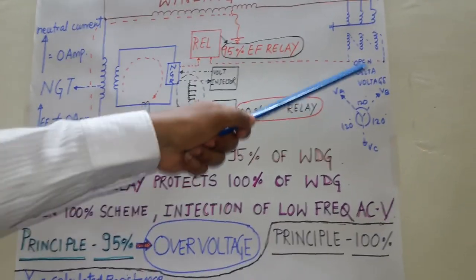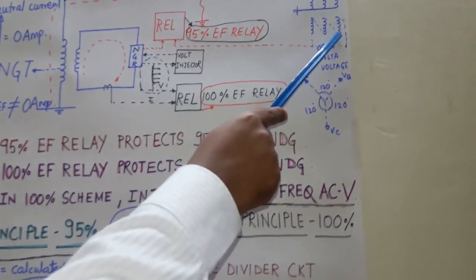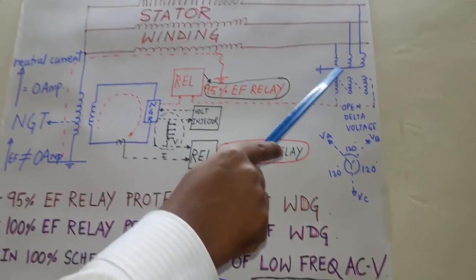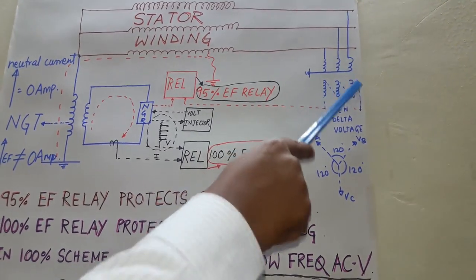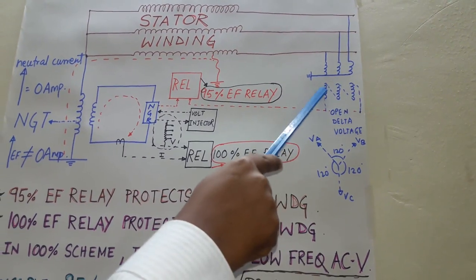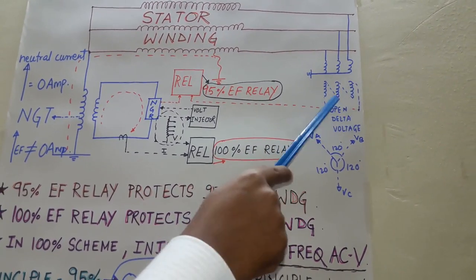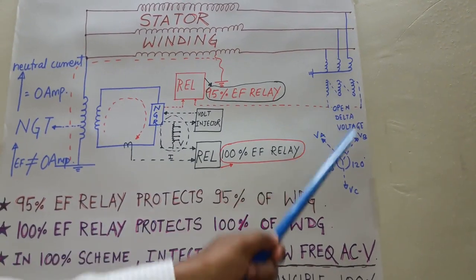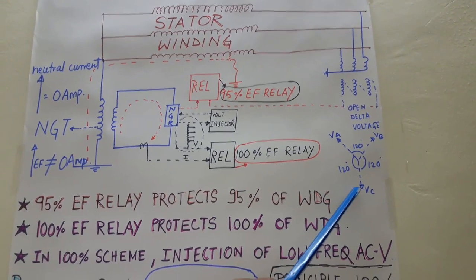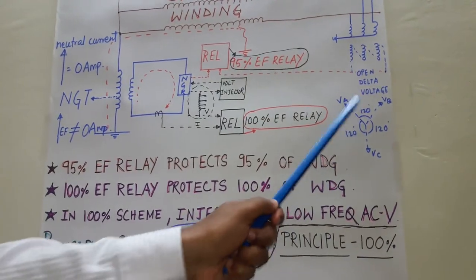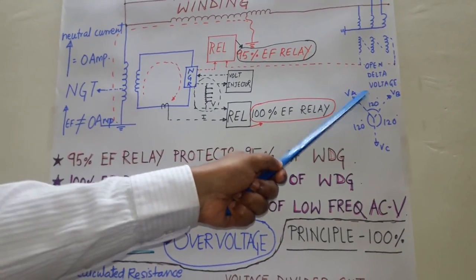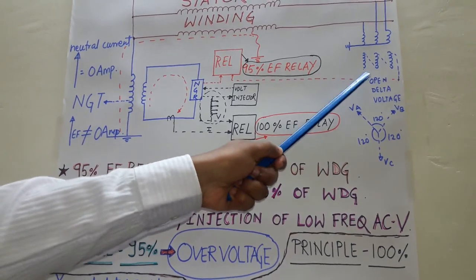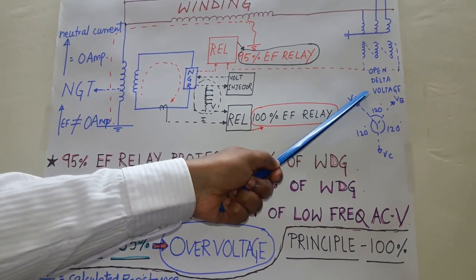Let me explain the concept of open delta voltage. You can see this is R phase, Y phase, and B phase. All three phases are added — head is connected to tail — giving us the summation of R, Y, and B. This summation is fed into the relay. During normal condition, the open delta voltage is zero because R, Y, and B voltages are equal in magnitude and have 120 degree angular separation, so there is no open delta voltage. But when there is an earth fault, an open delta voltage is seen due to the unbalance between R, Y, and B. So we can put one extra condition in the relay from the open delta side of the PT.